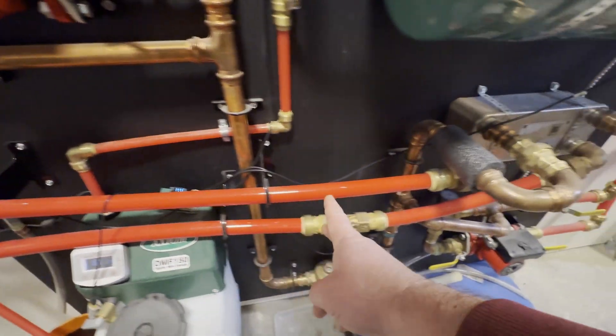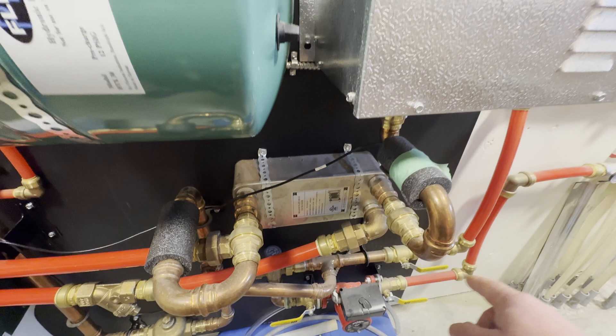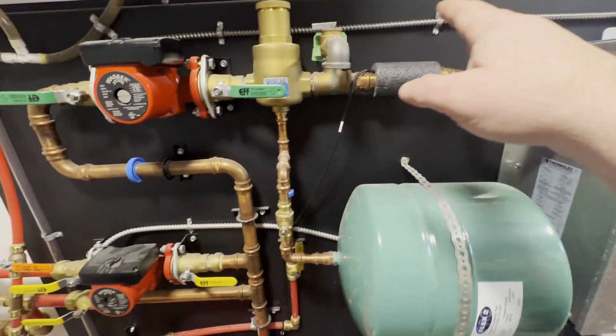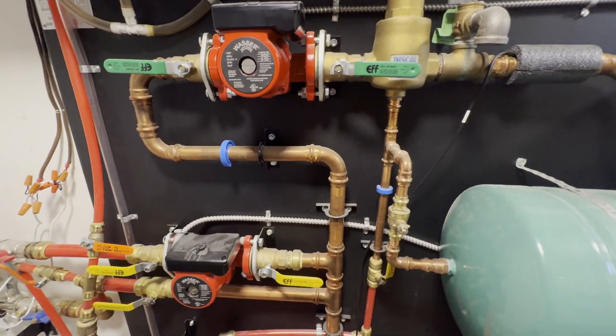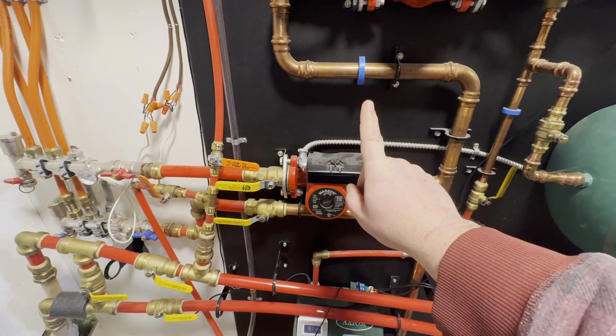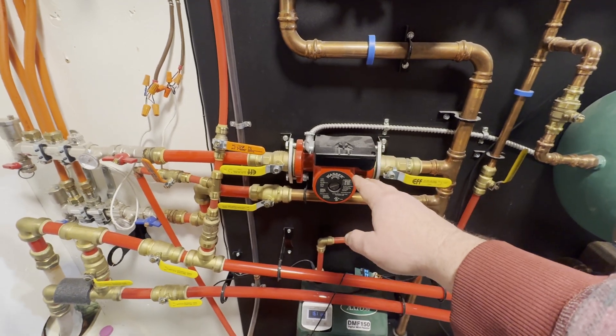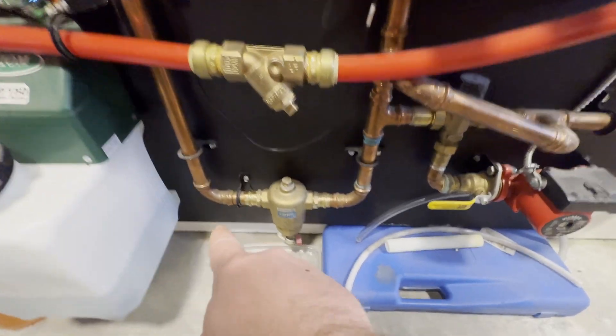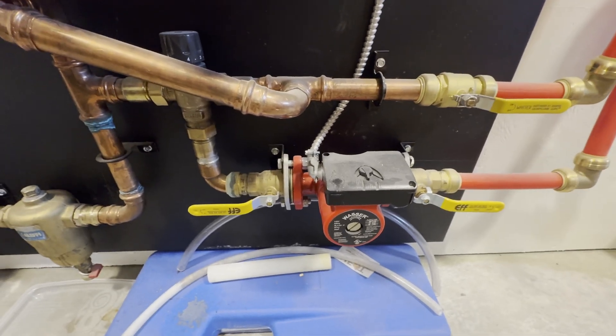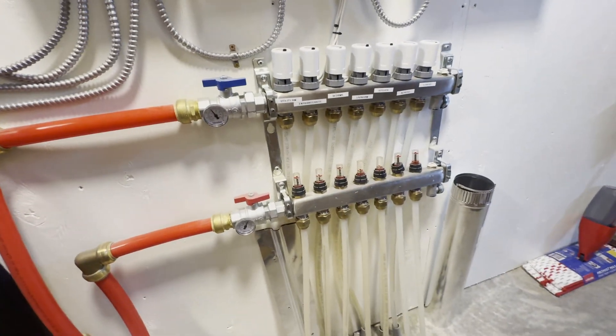These lines come along into a plate heat exchanger, and that heats the main loop up before it goes through the electric boiler and then comes out. This circulates the main loop. There's a hot loop that does upstairs zones — that gets the full boiler temperature up to about 180 degrees Fahrenheit. Then we come down, there's a separator, and then a mixing valve that mixes it down to 120 degrees Fahrenheit before it goes into all my zones for all of the slab.